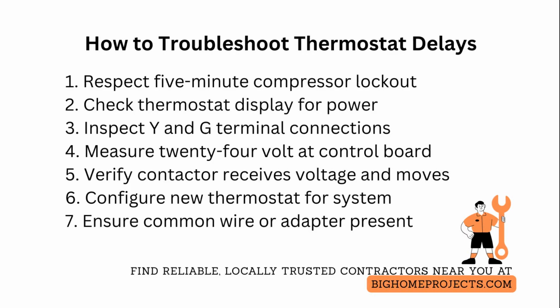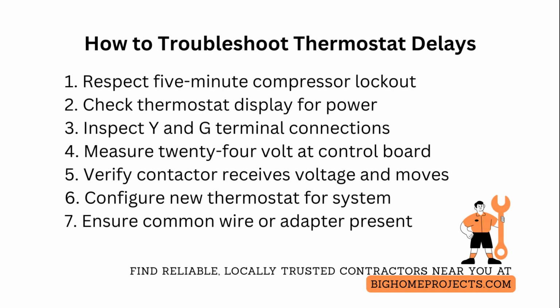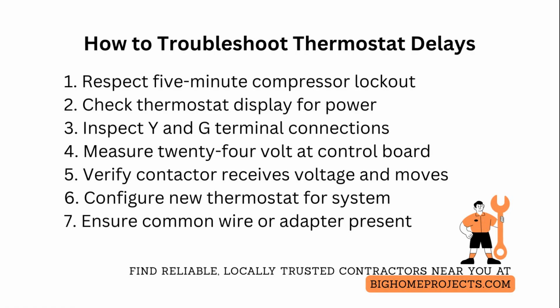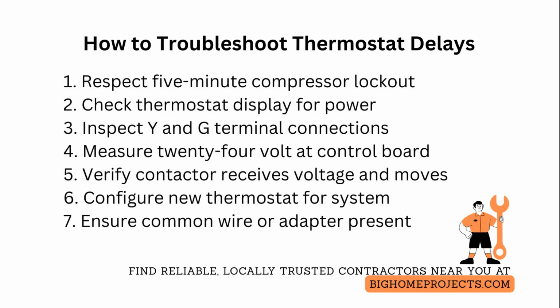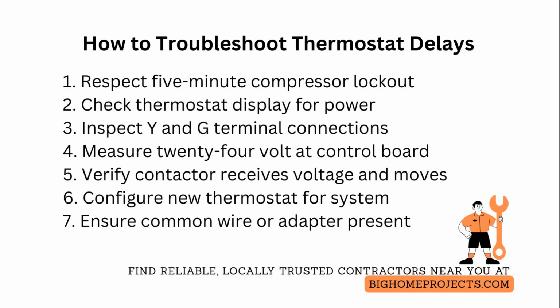At the air handler or condensing unit control board, check for 24 volts between the common terminal and Y and between the common and G using a multimeter set to AC volts. No voltage to Y means the thermostat is not completing the cooling call. If you see voltage at the control board but the condenser does not run, verify the contactor coil at the outdoor unit receives voltage and that the contactor is not mechanically stuck. A multimeter plus a manual press test will reveal that.